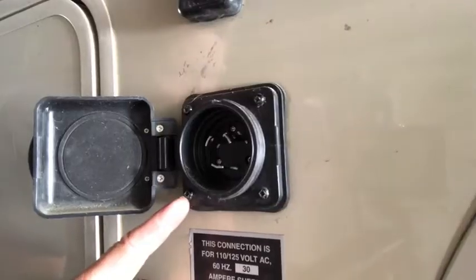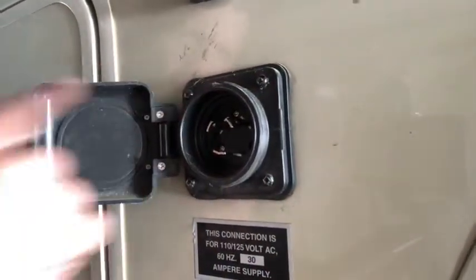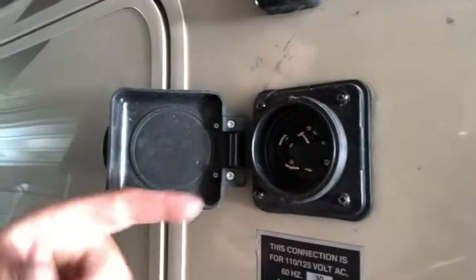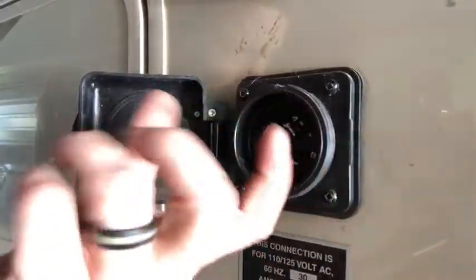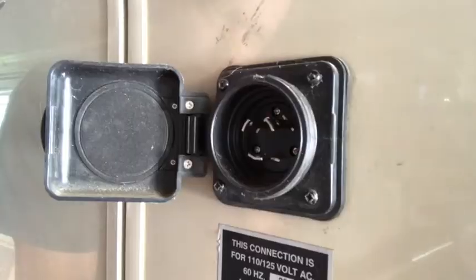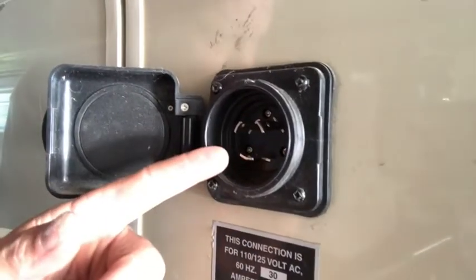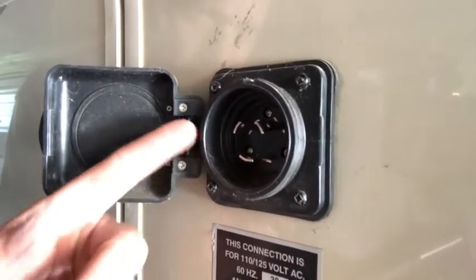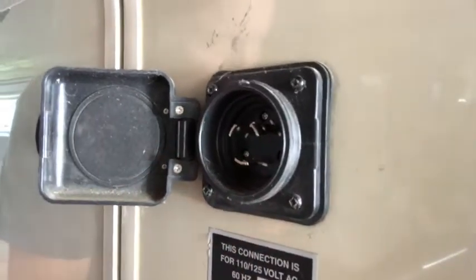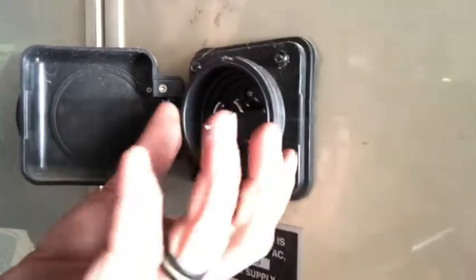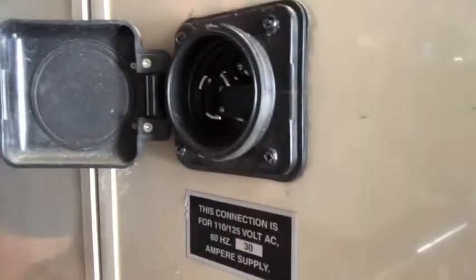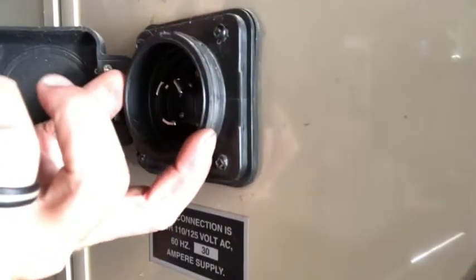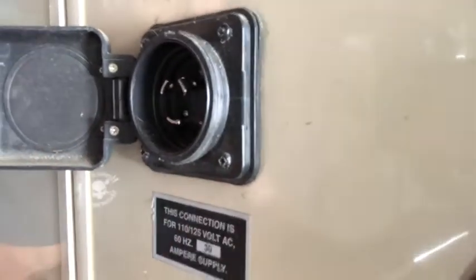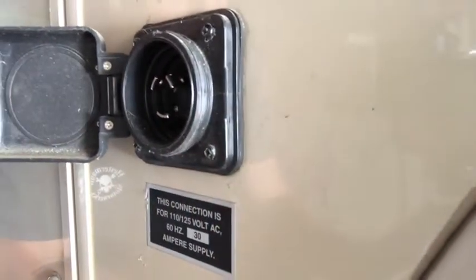So let me see if I can do this. Bear with me here. To take this receptacle off, there's 4 screws on each corner, and there may be some silicone around the edge, so even when you take those 4 screws out, it might take a little coercion to get it to come out of the rig. There should be 3 wires on the back side of this, so once these 4 screws are out, it won't just fall out. You should be able to pull it out a couple of inches, and you'll see those wires and where they attach on the back side of this receptacle.